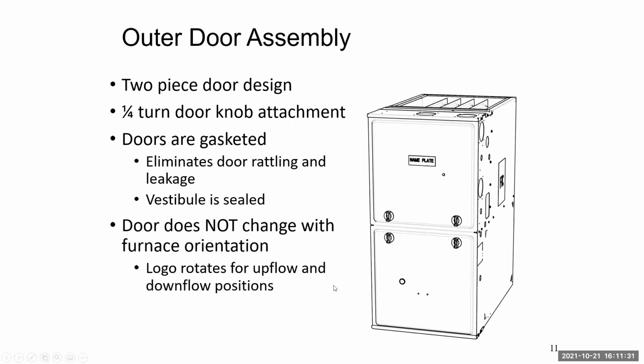The doors don't change with orientation of the furnace, whether it be upflow, downflow, anything. The thing that does change is that nameplate on there. You can flip that so that you're not putting a downflow furnace in, making it look upside down to the customer. Swap your nameplate over so it looks proper and professional to your customer.